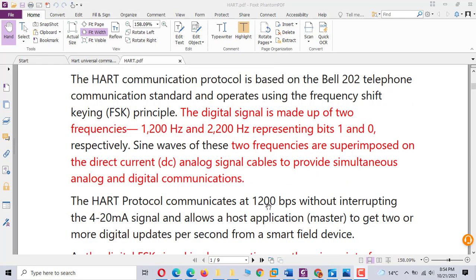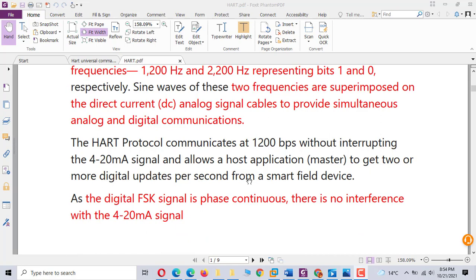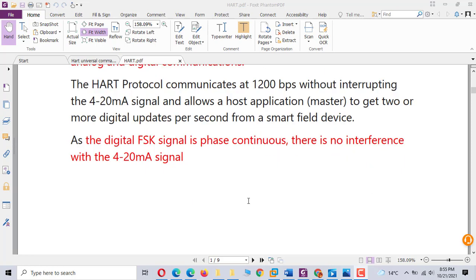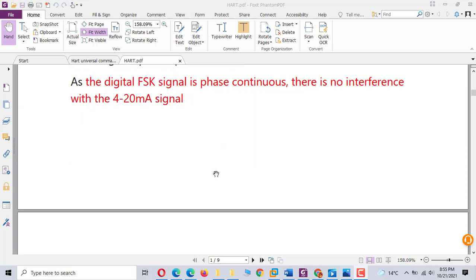So the two frequencies are superimposed on the direct current analog signal, capable of providing simultaneous analog and digital communication. HART communication uses 1200 bits per second without interrupting the 4 to 20 mA signal. There is no interference with the 4 to 20 mA signal.